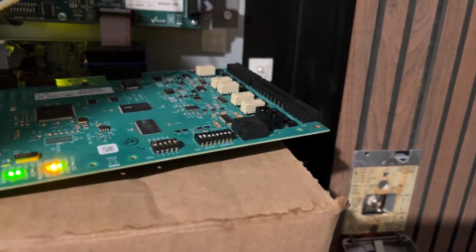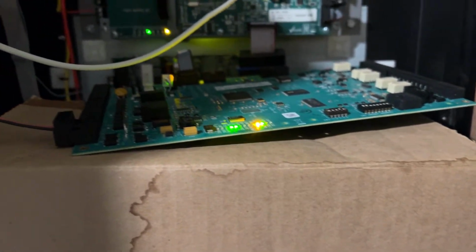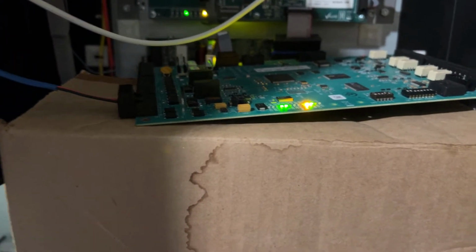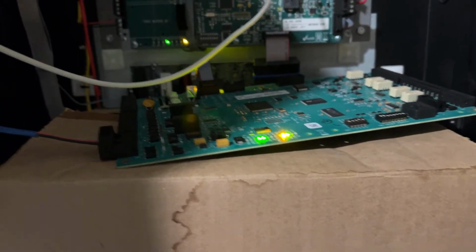And then I'm also showing all the SLC devices missing because they're down here. I don't have them hooked up. So that's good. I'll probably leave those troubles in for a little bit just to make sure that this doesn't go into network fault. But it's also showing node 64 missing, which is my NGA. This is the screen that I wanted to use on this system.